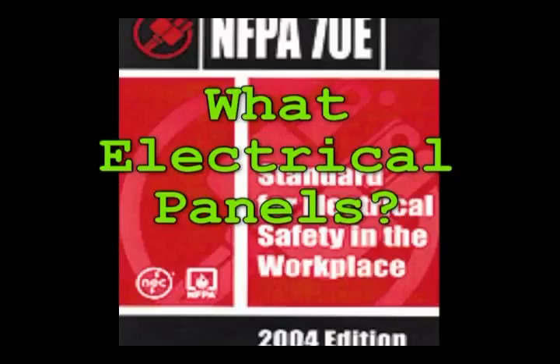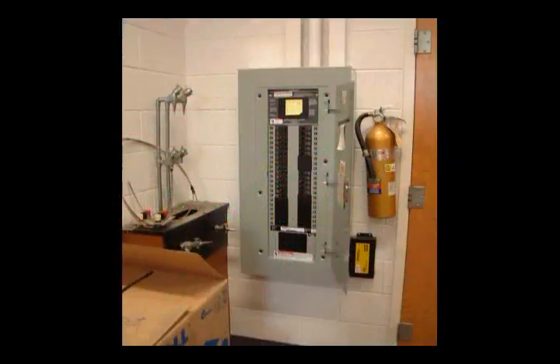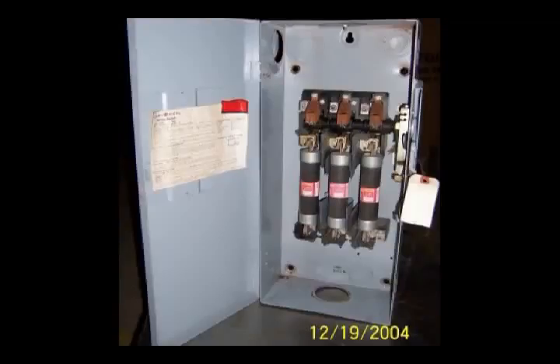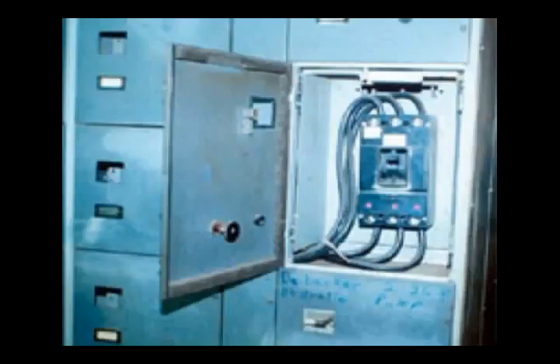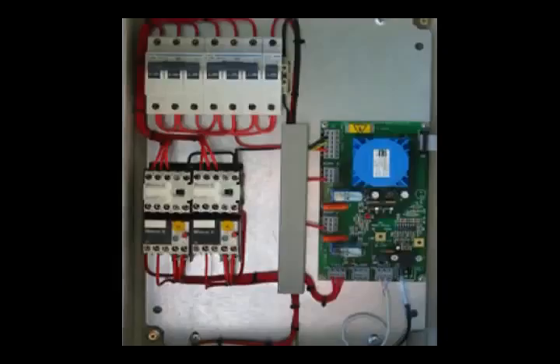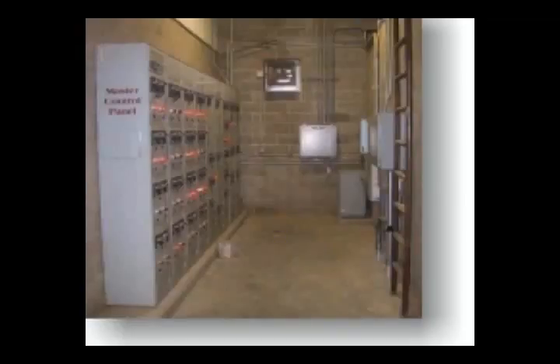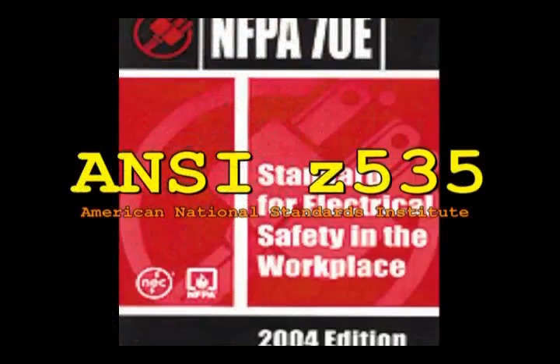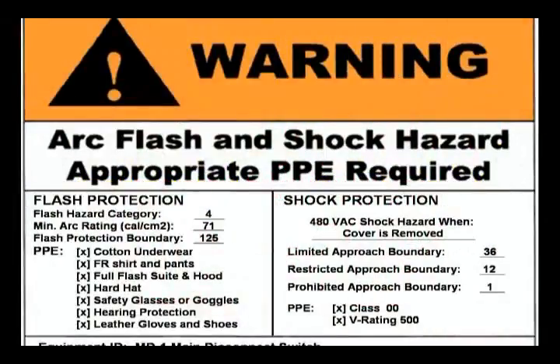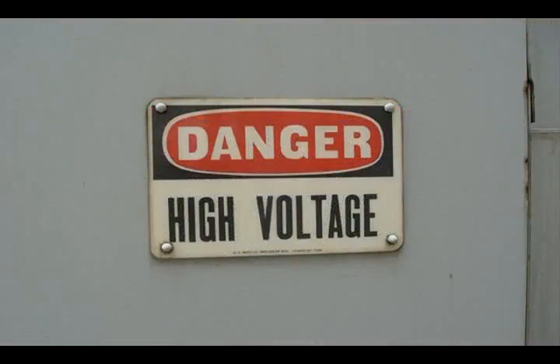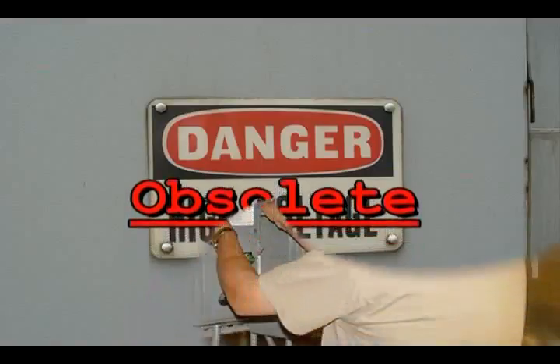Section 400.11 says that all switchboards, panel boards, industrial control panels, and motor control centers that are in other than dwelling occupancies and are likely to require examination, adjustment, servicing, or maintenance while energized shall be field marked to warn qualified persons of potential arc flash hazards. The marking shall be located as to clearly be visible to qualified persons before examination, adjustment, servicing, or maintenance of the equipment. Section 130.7e says that safety signs that meet the ANSI Z535 sign standard shall be used to warn employees about electrical hazards that might endanger them. That label looks like this. The ANSI Z535 sign standard calls this type of label obsolete.